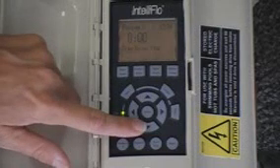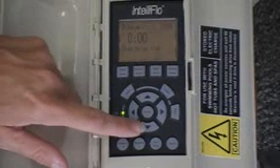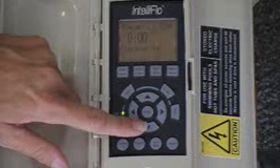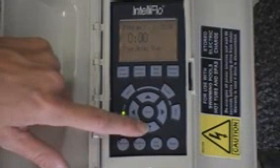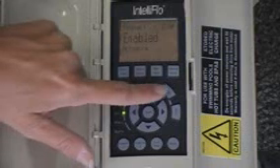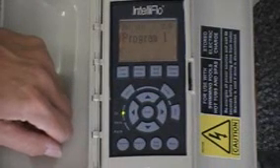If I hit my down arrow key, there would be a delay. That would be if you had an old heater, say, that needed to have a delay between the time it shut off. Right, where you want, when you turn off the pump and the heater turns off, you want the pump to continue running to cool off the water inside of the heater.